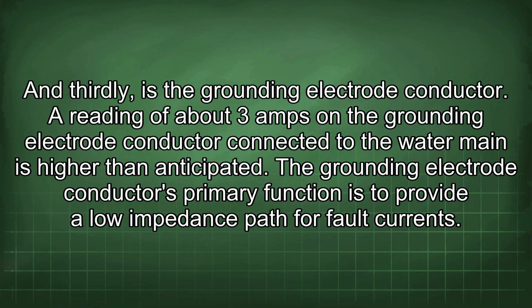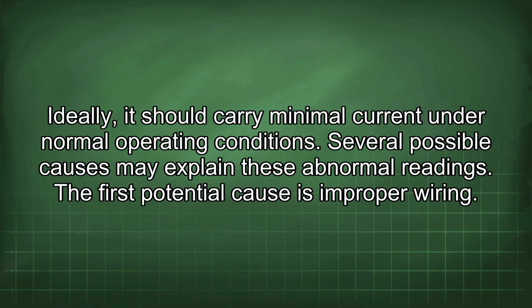And thirdly is the grounding electrode conductor. A reading of about 3 amps on the grounding electrode conductor connected to the water main is higher than anticipated. The grounding electrode conductor's primary function is to provide a low impedance path for fault currents. Ideally, it should carry minimal current under normal operating conditions. Several possible causes may explain these abnormal readings.